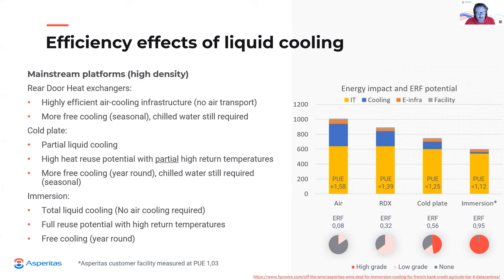In addition, cold plate allows the reduction of IT footprints due to the capture of heat within the chassis, which means that the internal cooling systems of a server are no longer managing the chip heat, but they are still required because all other components are not cooled by the same cold plate. Because of this, cold plate is often combined with rear door coolers to allow full capture of all the heat at rack level. This also means that part of the rack still requires low temperature cooling while other parts can operate with elevated temperatures. Approximately 60% of the IT energy can operate with elevated temperatures while the rest remains cold water cooled.